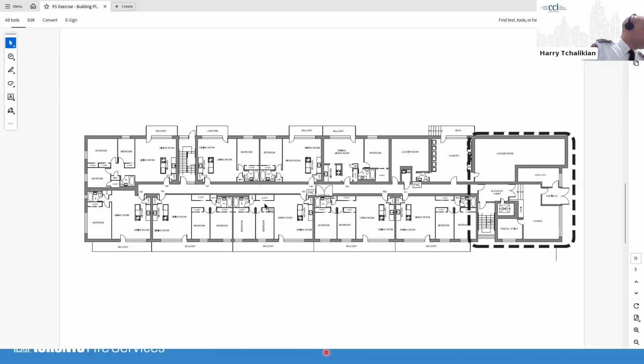Sentence 4. Where a forced air fuel burning appliance provides heated air to a building but is not located within a residential occupancy or care occupancy, a carbon monoxide alarm shall be installed: A, in the service room or area where the appliance is installed if the appliance is located in the building; B, in the public corridors serving suites of residential occupancy where the corridor is directly heated by forced air fuel burning appliances, including one, at least one carbon monoxide alarm in each portion of a divided corridor, and two, each carbon monoxide alarm in an undivided portion of a corridor is spaced not more than 25 meters apart; C, adjacent to each sleeping area within each suite of a residential occupancy or care occupancy directly heated by the forced air fuel burning appliance; and D, on each story without a sleeping area within each suite of a residential occupancy or care occupancy directly heated by the forced air fuel burning appliance.